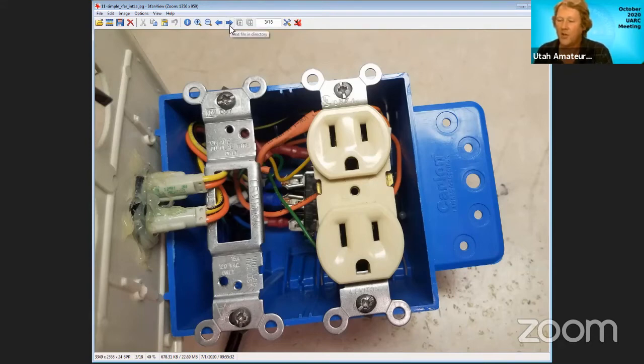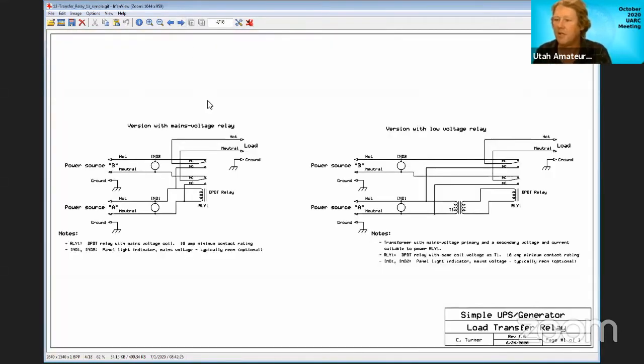It blew up the UPS and blew fuses and everything on the transformers. So we got another UPS, but it also tended to weld the contacts on this relay. The reason was it was just beating it to death. So I built a slightly fancier version than this one.